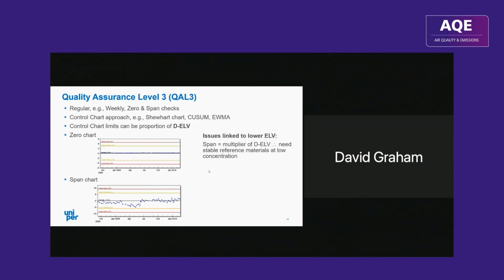Why does a lower ELV matter? Well, we need stable reference materials at low concentrations. That's the first point. And also, the control limits are often based on the daily limit value, again the proportion of the daily ELV. So there's a possibility of increased failure rates if the current performance is close to the existing control limits. And of course, that might well be indicating you need new CEMS at that point, new AMS.